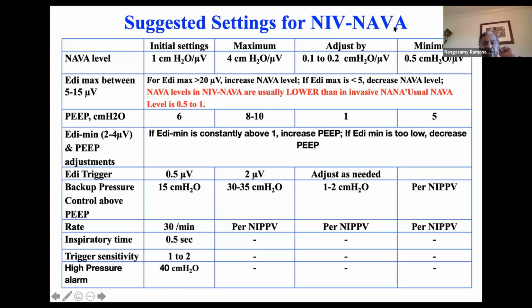So these are the suggested settings for NIV-NAVA. How do you start? I start with a NAVA level of 1. Maximum is 4. You adjust by 0.1 to 0.2 centimeters. If the PIP is low, baby is retracting, and EDI peak is less than 5, you want to shoot for between 5 to 15, right? So minimum is 0.5 centimeters. In fact, if the baby is on 0.5 centimeters of NAVA, doing well, you can switch the baby to Si-PAP from NIV-NAVA.